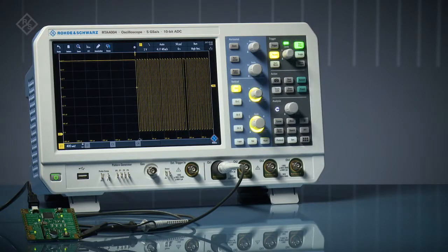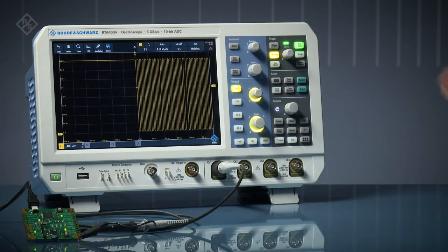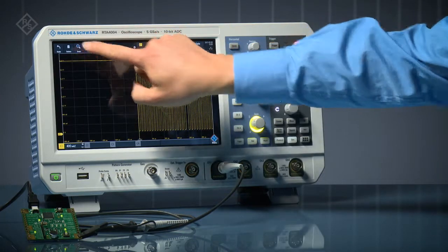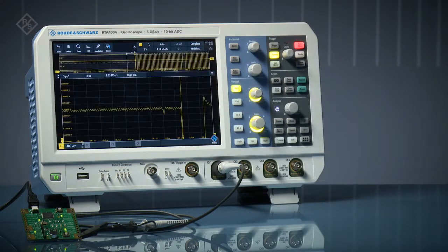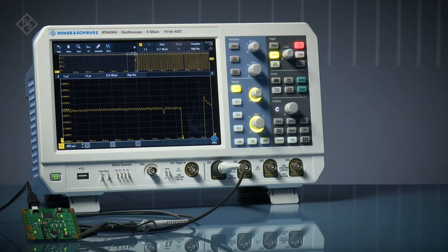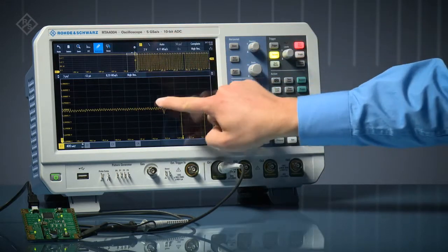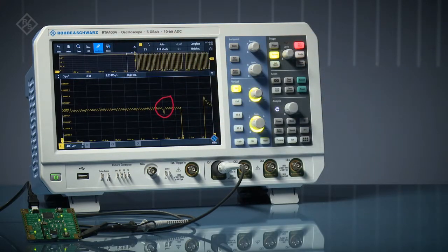RTA 4000 series oscilloscopes feature vertical zoom. Simply draw a box around the portion of the signal you want to magnify. Combined with the instrument's 10-bit ADC, vertical zoom allows you to find small signals in the presence of large amplitudes like this one.